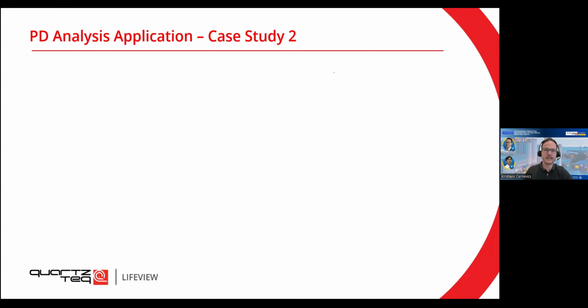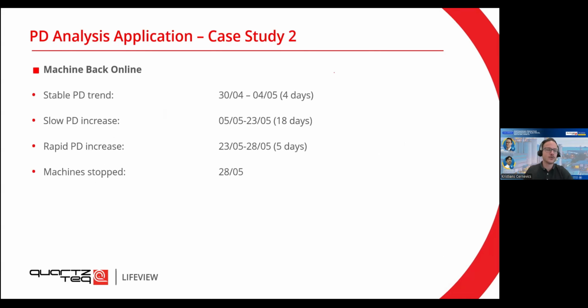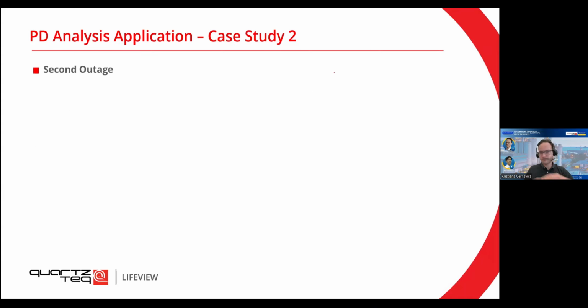And I think the next slide actually tells you that, yes, we managed to see a stable trend for 4 days, a slow increase for 18 days, already a bit quite fast. And then finally, at the end of May, for 5 days, there was a very, very rapid PD increase. And this is when the decision was made that the machine needs to be stopped, because it would have been essentially a catastrophic failure. So altogether 28 days after this first intervention where we saw this extensive damage and then started to monitor the PDs, after 28 days, we had enough data to convince the client that the machine needs to be shut down. Otherwise, there would be failure.